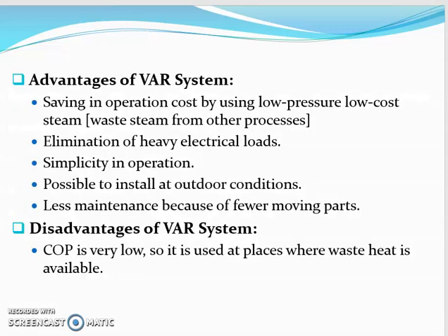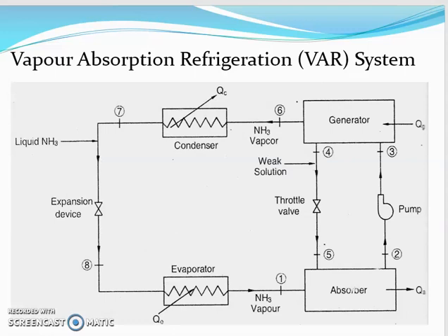Now coming back to advantages. The advantages of the VAR system: it saves operation cost by utilizing low pressure, low cost steam. Over here, this is a heat operated device. Why? Because in the generator we supply only heat, and work is needed only at the pump, which is very little. So this is basically a heat operated system.